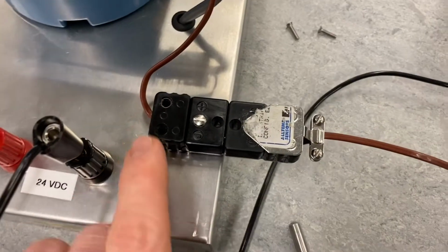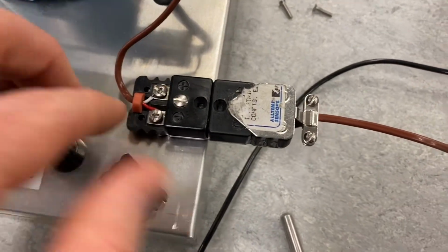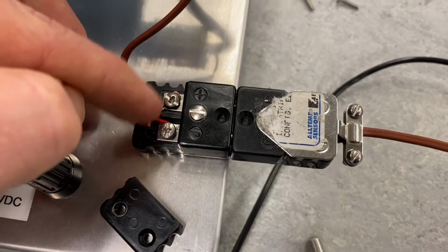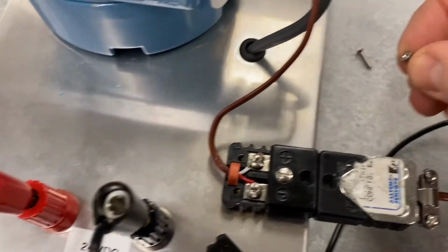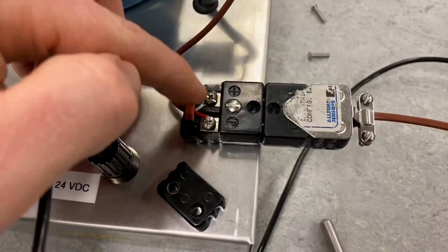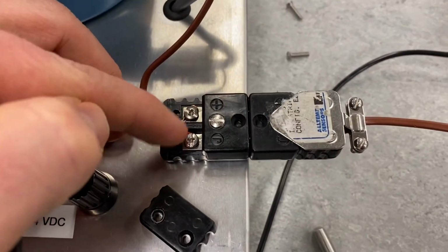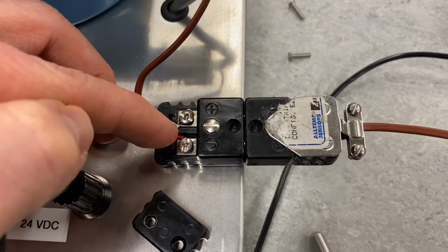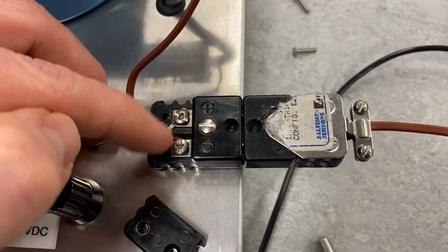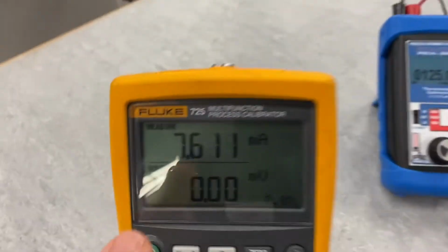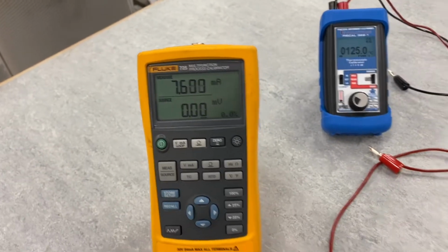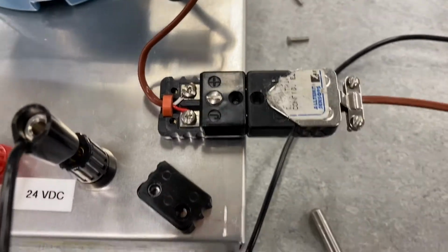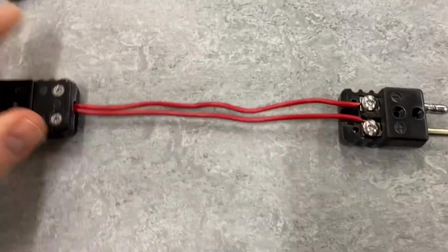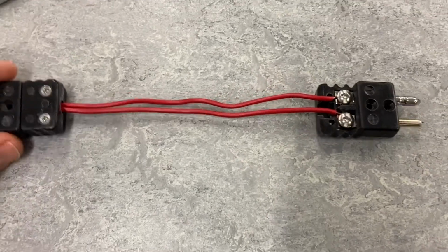So in the next part of this lab, we're going to be removing this cover right here for the thermocouple connector to expose the wire junction here. And we just have to take out these screws. Because what we're going to need to do, we need to access this, because we're going to be cooling this junction with either a cold air gun or a bag of ice to drop the temperature here. We want to see what it does to our milliamp value over here on our Fluke. So we're going to do it there, and then in the next step we're going to be removing this and placing these copper extension wires in the loop here.